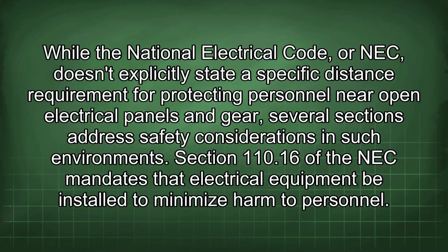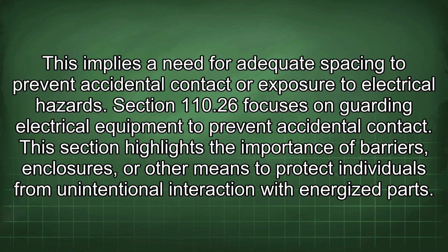While the National Electrical Code, or NEC, doesn't explicitly state a specific distance requirement for protecting personnel near open electrical panels and gear, several sections address safety considerations in such environments. Section 110.16 of the NEC mandates that electrical equipment be installed to minimize harm to personnel. This implies a need for adequate spacing to prevent accidental contact or exposure to electrical hazards.